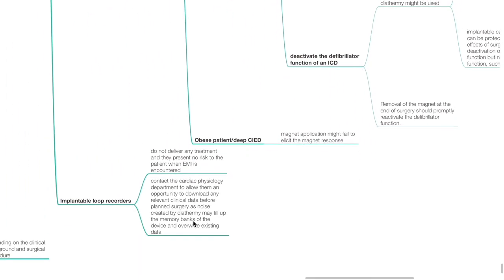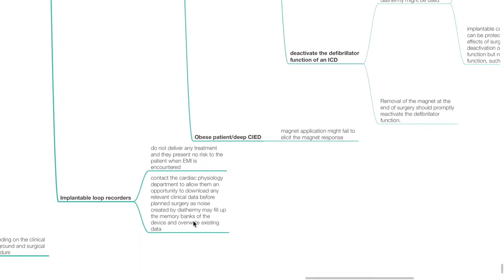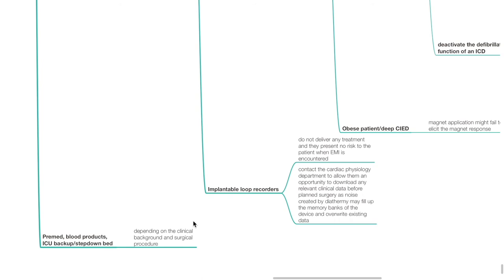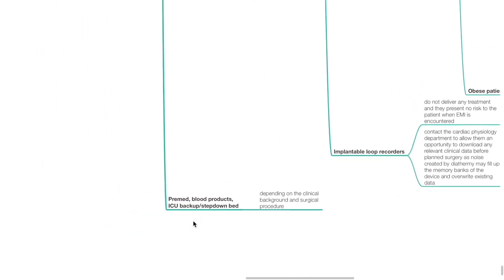Implantable loop recorders do not deliver any treatment and present no risk to the patient when electromagnetic interference is encountered. Contact the cardiac physiology department to allow them to download any relevant clinical data before the planned surgery, as noise created by diathermy may fill up the memory banks of the device and override existing data. Pre-med, blood products, ICU backup or step-down bed depends on the clinical background and the surgical procedure.